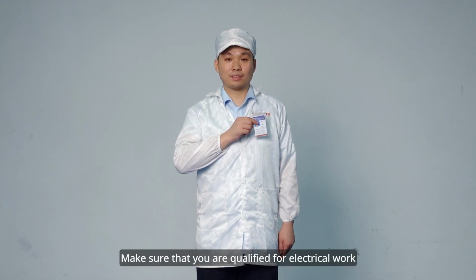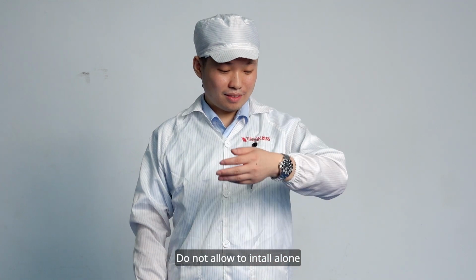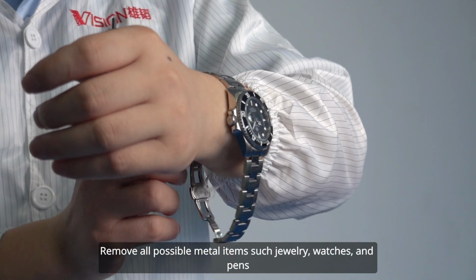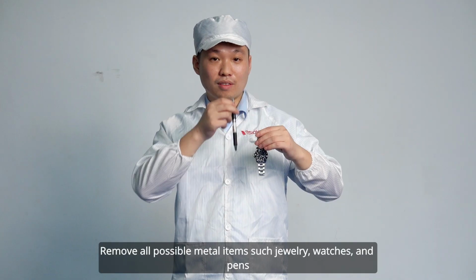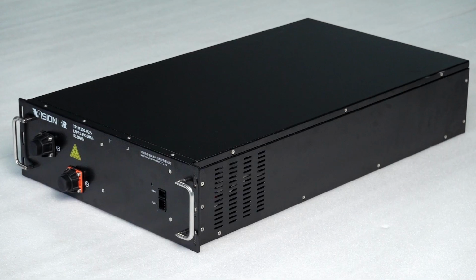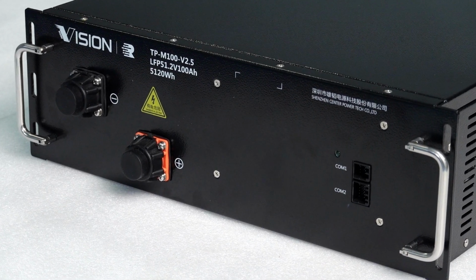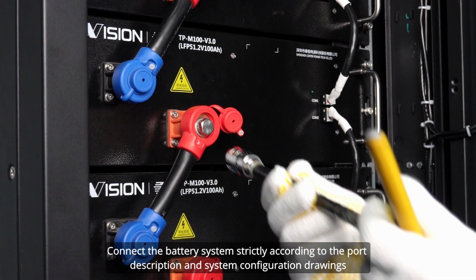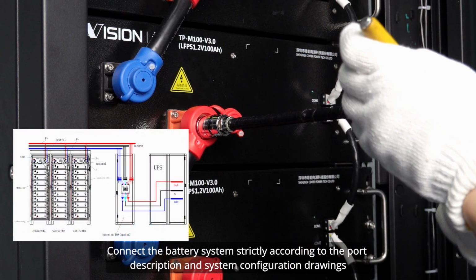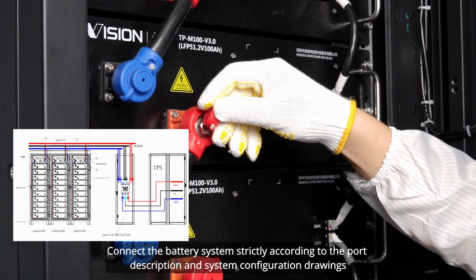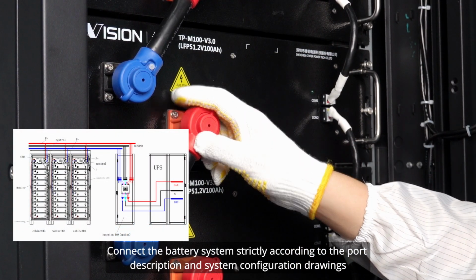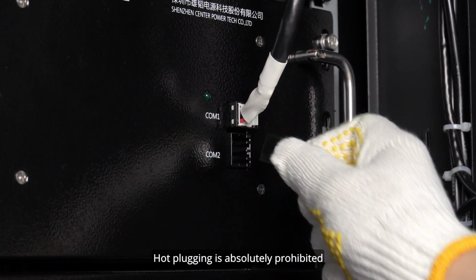1. Safety precautions. Make sure that you are qualified for electrical work. Do not install alone. Remove all possible metal items such as jewelry, watches, and pens. Connect the battery system strictly according to the port description and system configuration drawings. Hot plugging is absolutely prohibited.